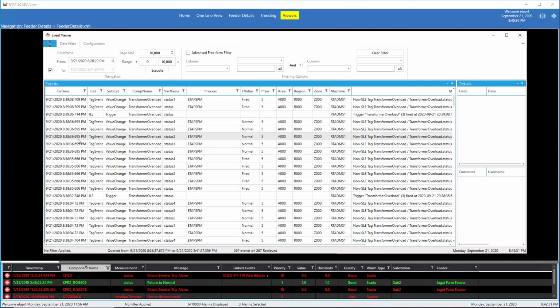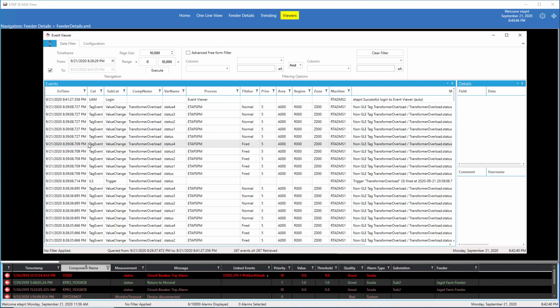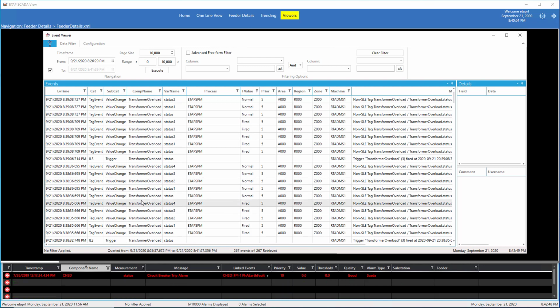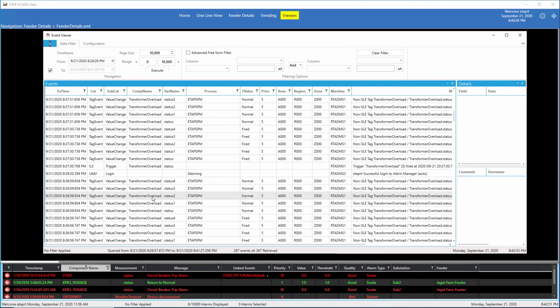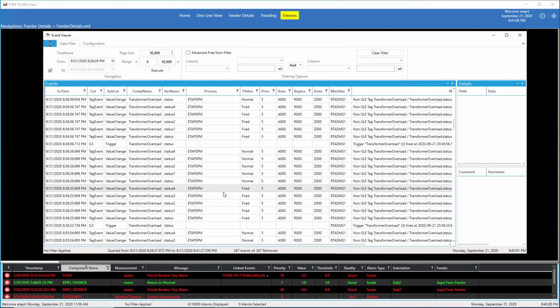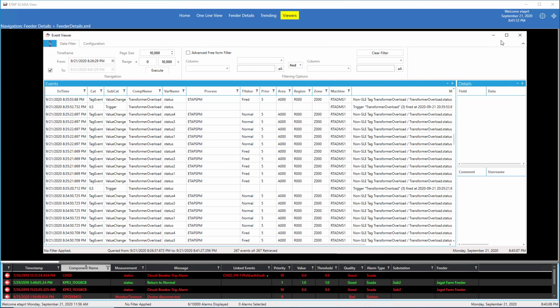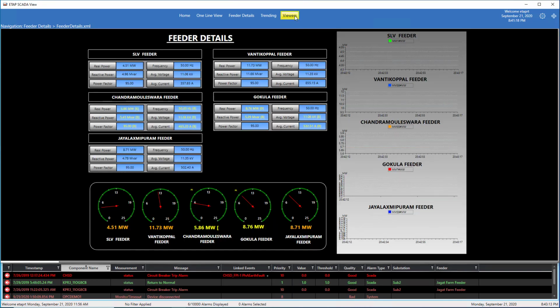That means the device that tripped the unit, or for example the relay, or the device that's monitoring the unit. So that information allows us to do a very detailed sequence of event analysis. The information here will include, for example, the components that get tripped. On many occasions, if this was sent by a component protection signal, that information will also get recorded. So this, as I mentioned, gives you a very detailed historical view of what's going on in the substation.